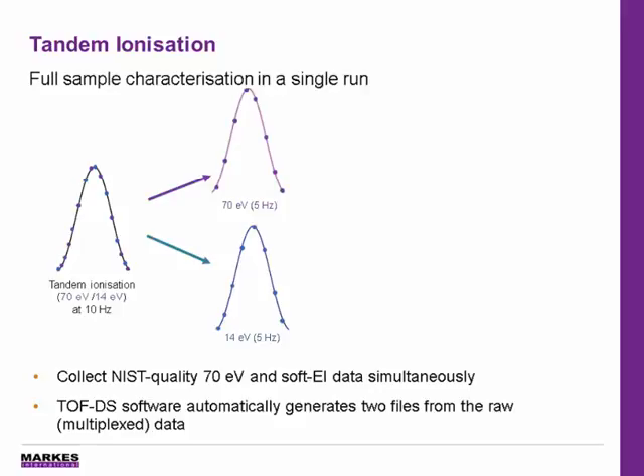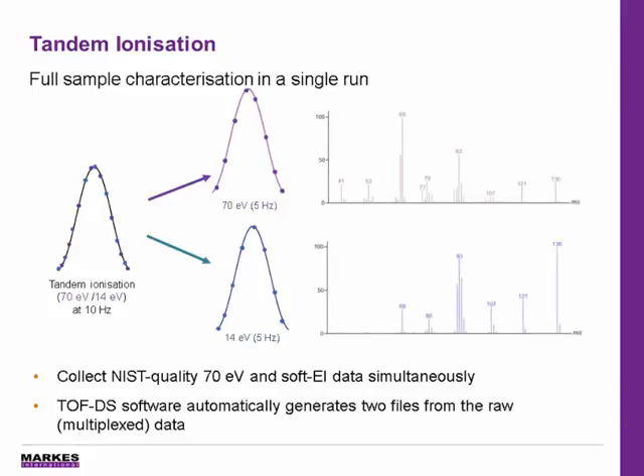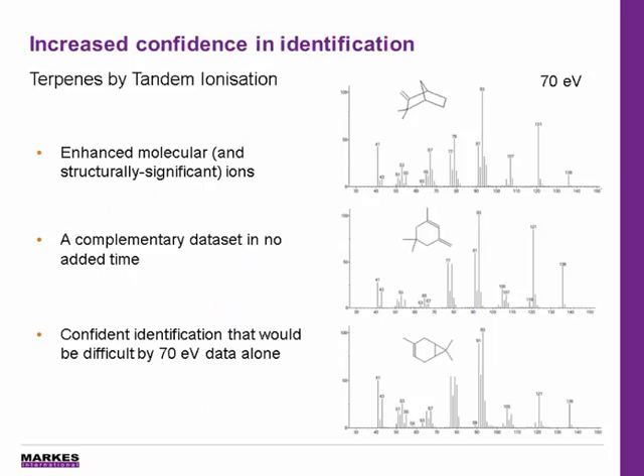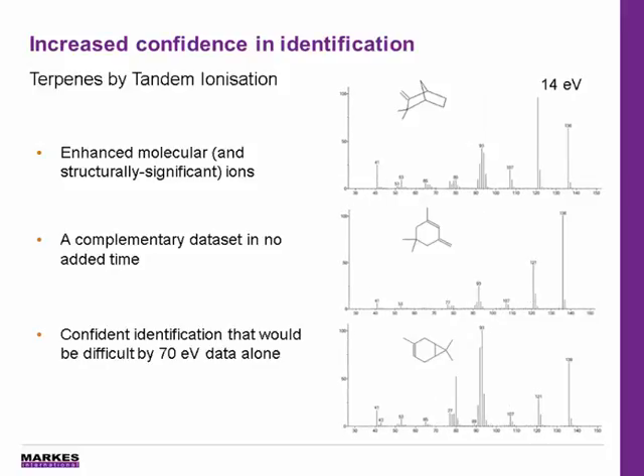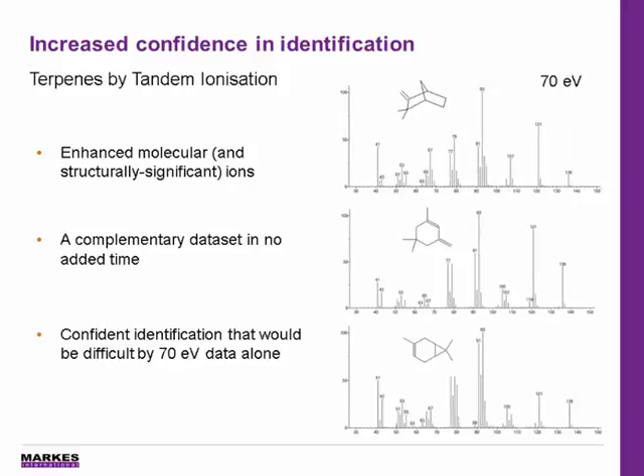Reference quality 70 eV spectra can be screened against commercial or in-house libraries, while soft EI with improved molecular ions and reduced fragmentation gives enhanced confidence in compound identification. This is especially true for isomers. Soft EI retains a degree of fragmentation, unlike other soft ionization techniques, meaning that the molecular ion and other structurally significant ions are enhanced, which can help to identify individual isomers, like the terpenes shown here.